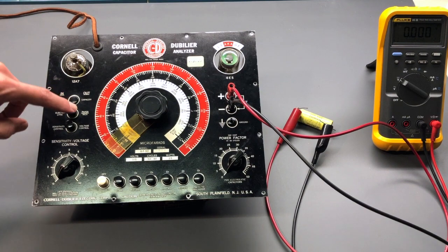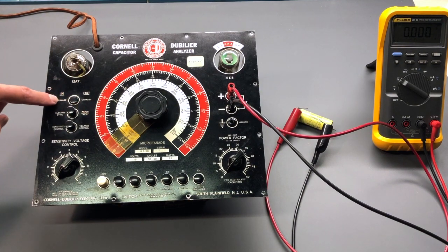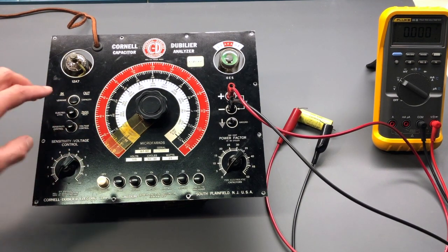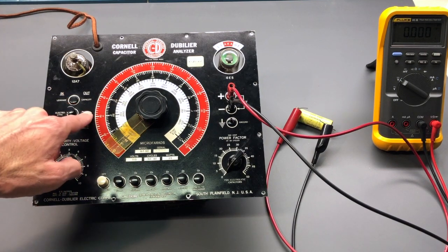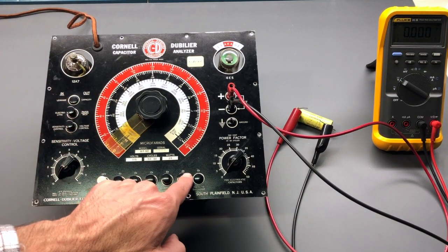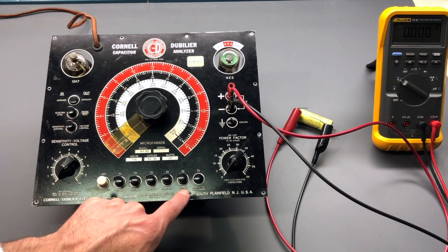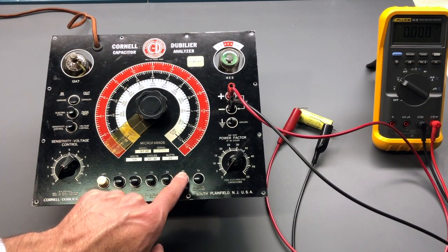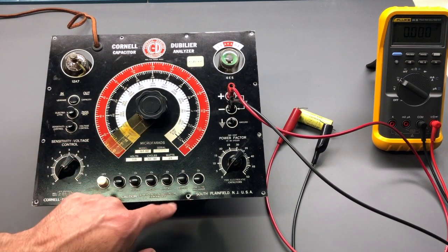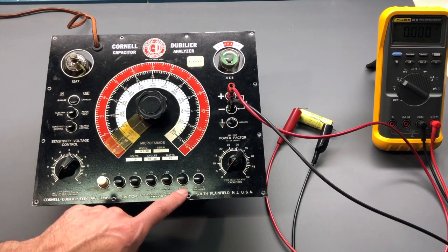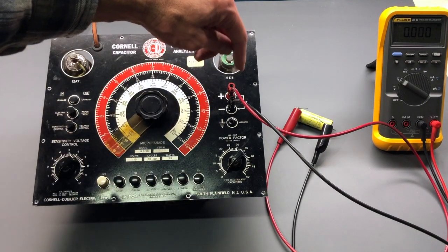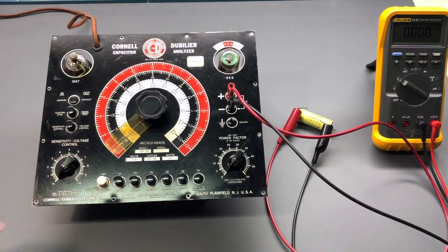So this is in the paper and mica setting in the leakage mode. And in that position of leakage and paper mica, only this C5 button, which said 400 to 600 volts with C5, you press this button to run the test. However, it does not put 400 to 600 volts, anything in that range, out to these test jacks. We'll take a reading and see what actual voltage is on these terminals during the test. I'm not sure what it is. I selected a capacitor with a 600 volt rating because I knew that was well above what this tester could supply.